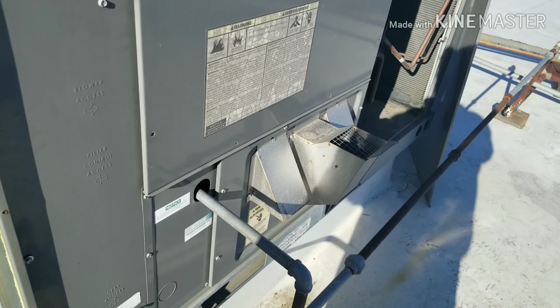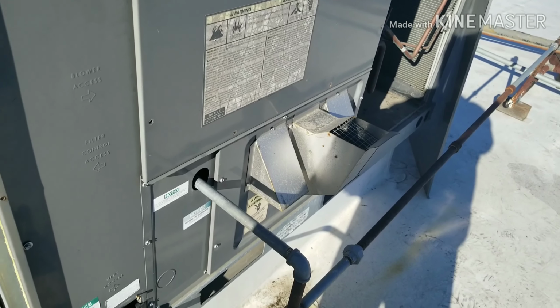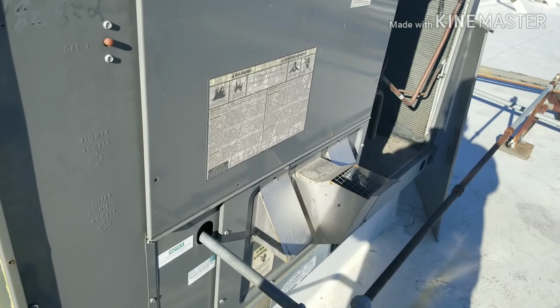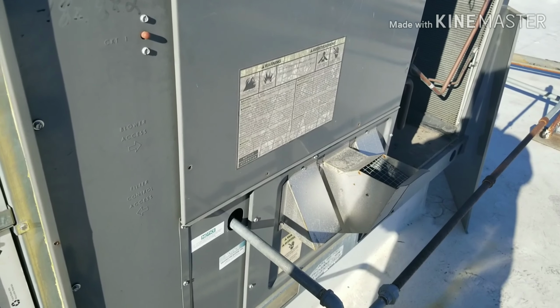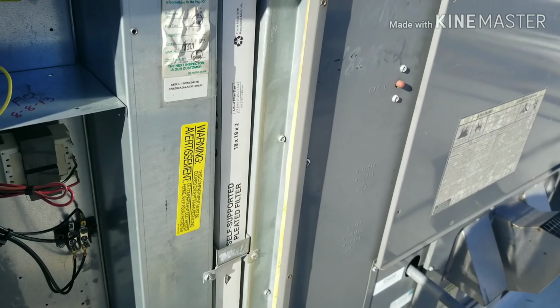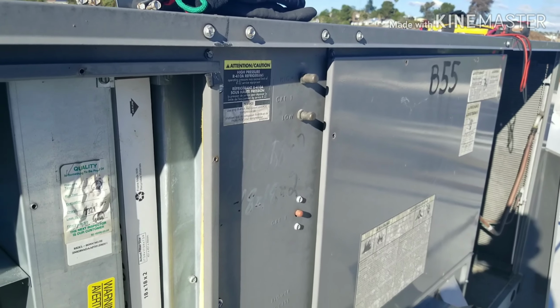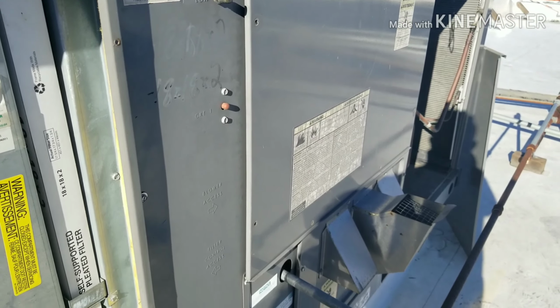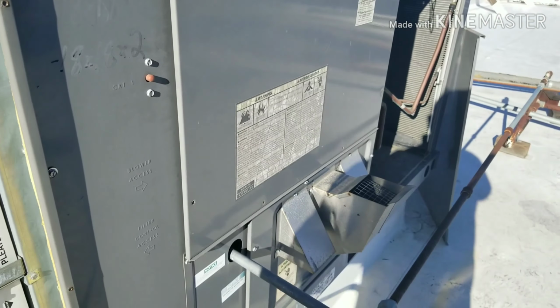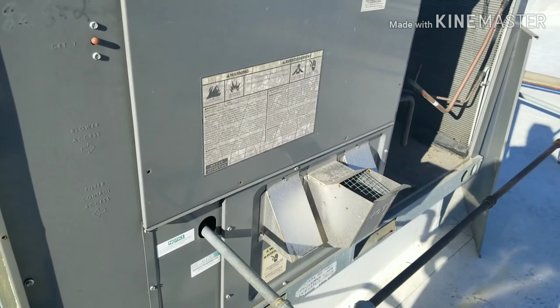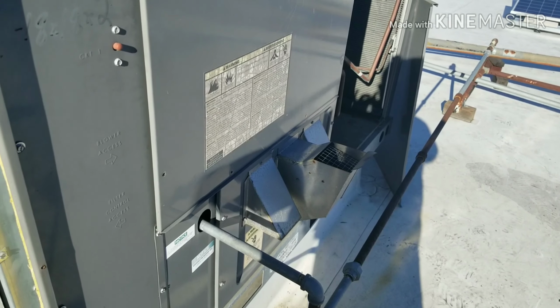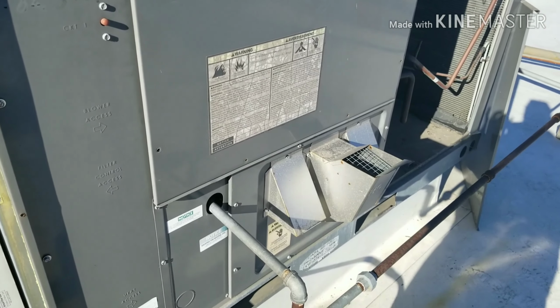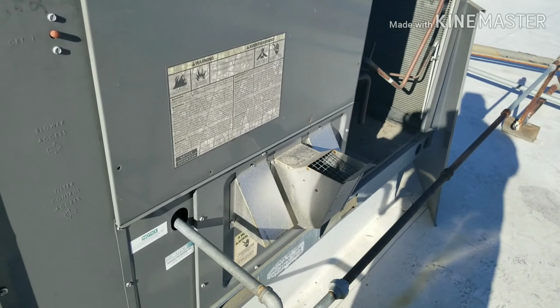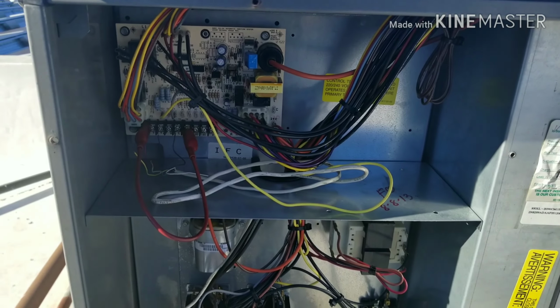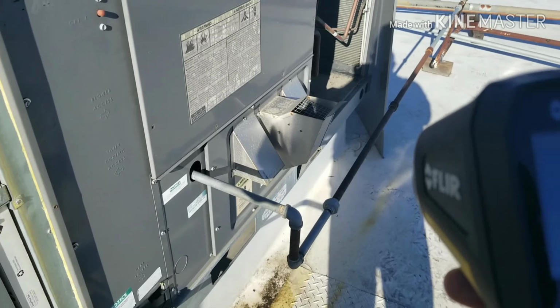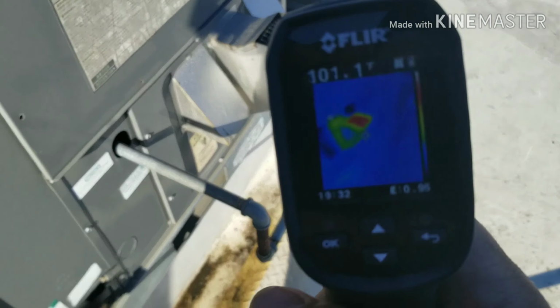And you're gonna hear the spark, and then the gas valve turn on. There's a spark. And there's the gas. It's gonna be a minute, and then the fan is gonna turn back on as it goes up to temperature. And we're gonna check the temperature on the stack right now, so you guys can see what the temperature is. It goes up to 200. So here we go. There's a stack.